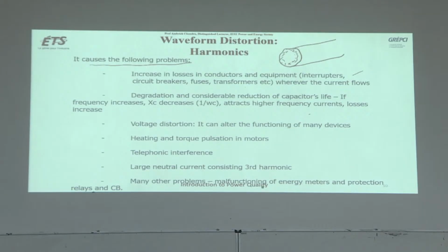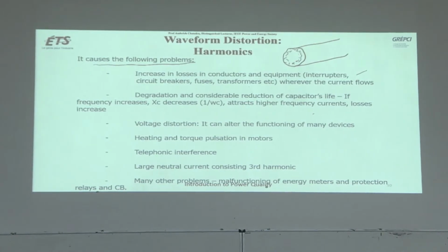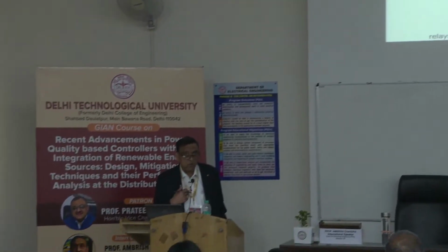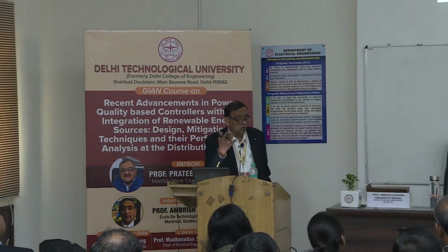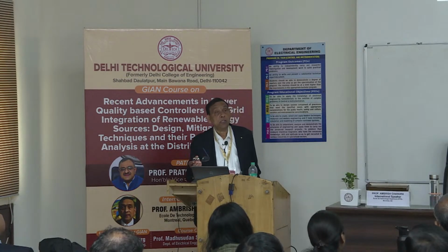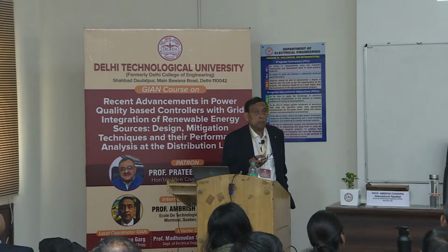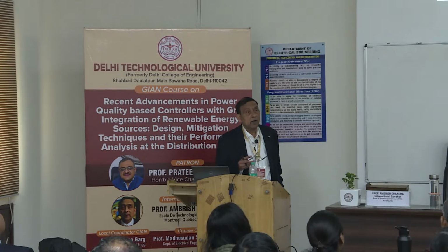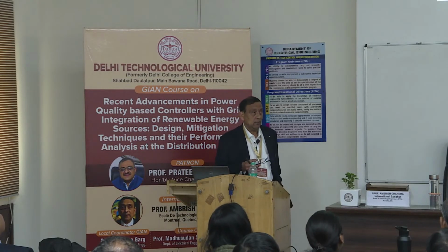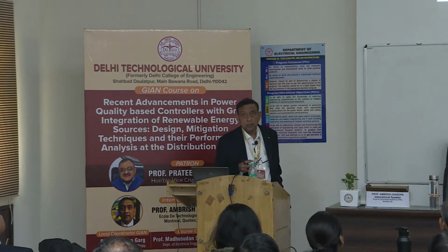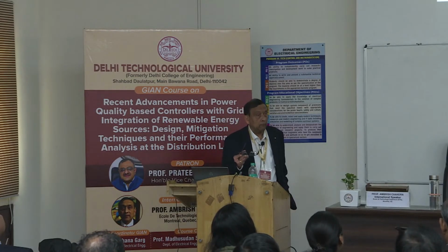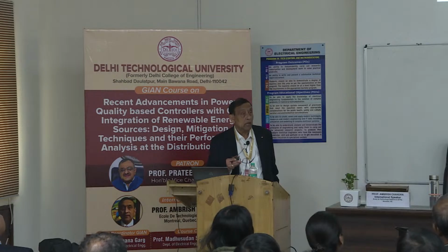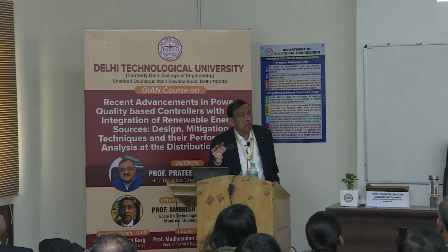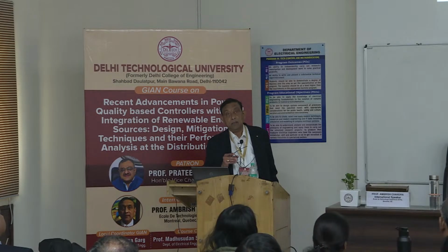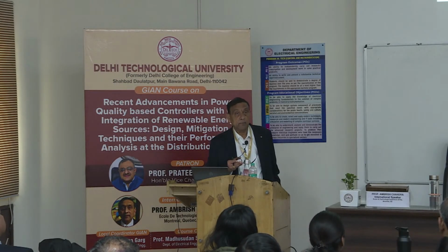But then you have electromagnetic losses also, like hysteresis losses or eddy current losses in the core of the transformer or the core of the machines. Hysteresis losses are proportional to the frequency, and eddy current losses are proportional to the square of the frequency. Suppose you have a fifth harmonic, then hysteresis losses will increase 5 times in the core. But eddy current losses will be 25 times more. This will heat up the transformer, and you cannot load the transformer to its full capacity.